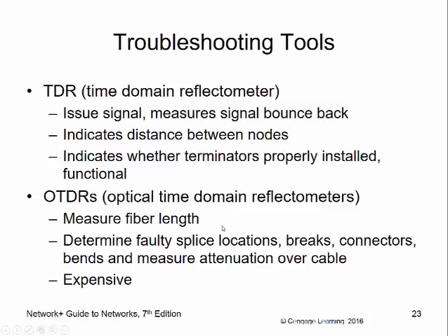OTDR, same idea, except it's for fiber optics. It's an optical TDR. Instead of sending an electrical signal down the wire, it's sending a beam of light. Same thing. It gets bounced back off the other side, and it tells you how long it took, tells you how far away your break is. It can also tell you things like bad connectors, bad splices, all that kind of stuff.